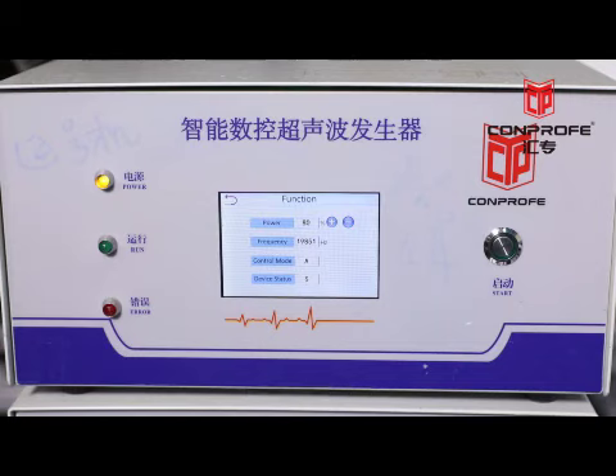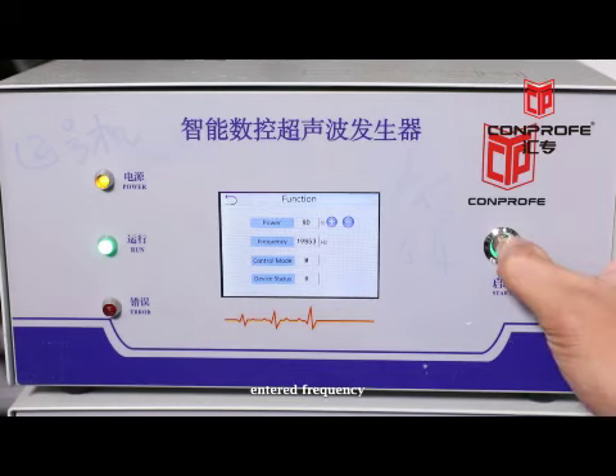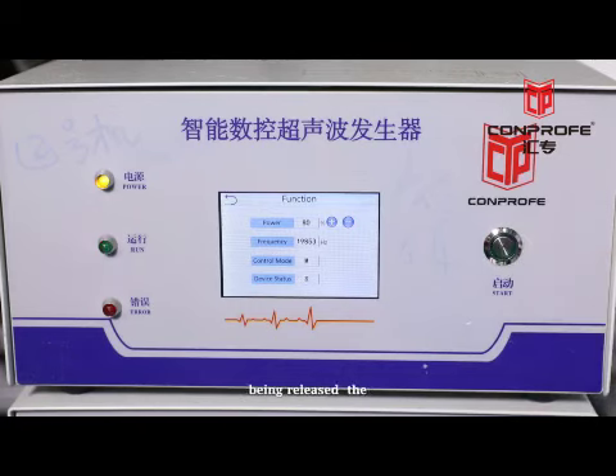Manual mode. Click on frequency to enter the operating frequency manually and press down the control port's run button. Then, the running indicator light becomes normally on and the generator starts to run at the manually entered frequency. After the run button is released, the running indicator goes out and the generator stops working.